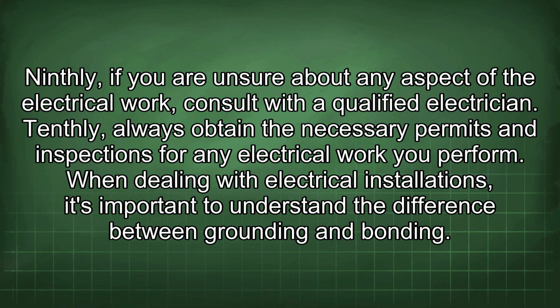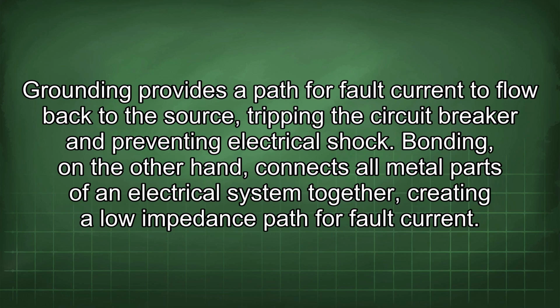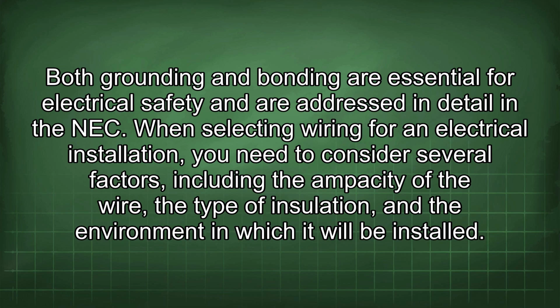When dealing with electrical installations, it's important to understand the difference between grounding and bonding. Grounding provides a path for fault current to flow back to the source, tripping the circuit breaker and preventing electrical shock. Bonding, on the other hand, connects all metal parts of an electrical system together, creating a low impedance path for fault current. Both grounding and bonding are essential for electrical safety and are addressed in detail in the NEC.